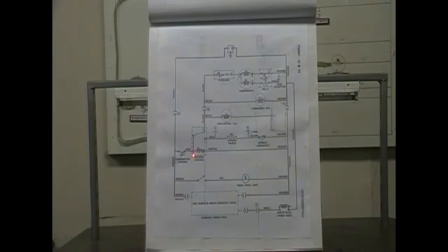Let's back up to the defrost control. You have four terminals. You got terminal 1, terminal 3, terminal 2, and terminal 4. Terminal 1 and 3 is for your defrost control motor. Terminal 1 is common, as we see. Terminal 3 is connected to your hot wire.